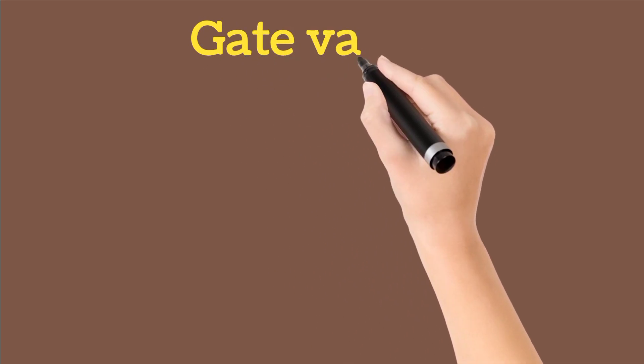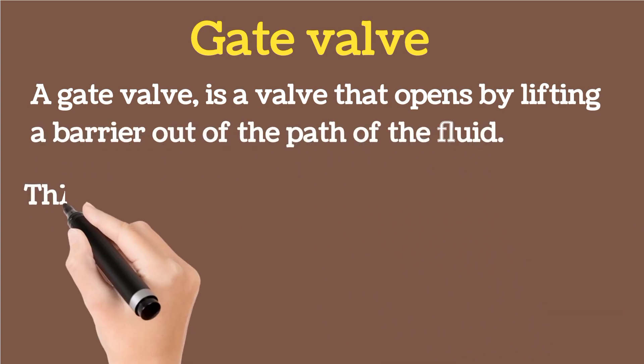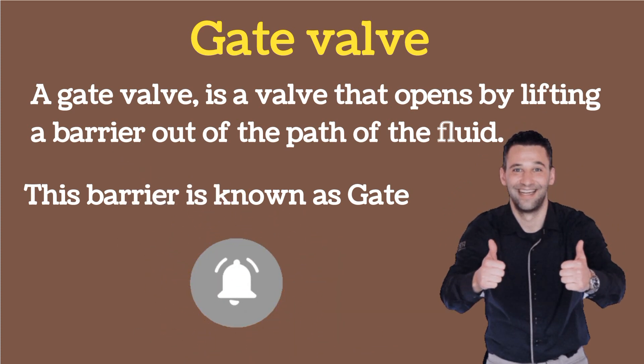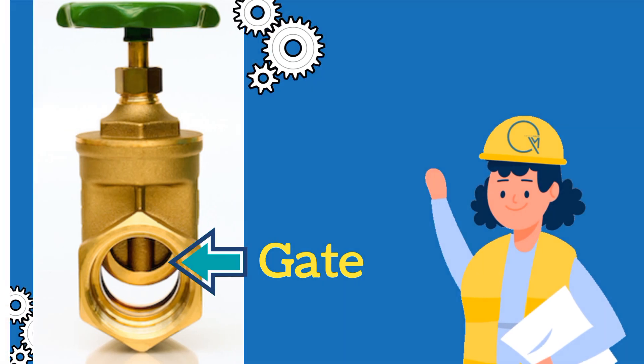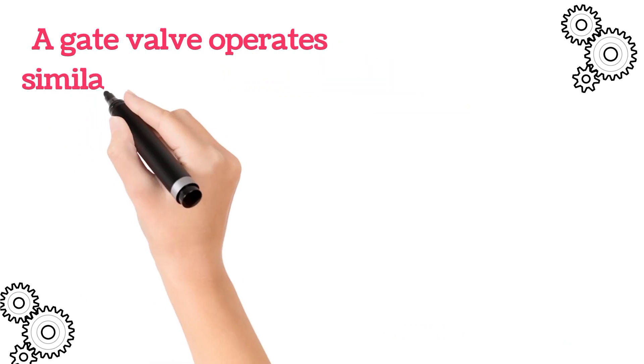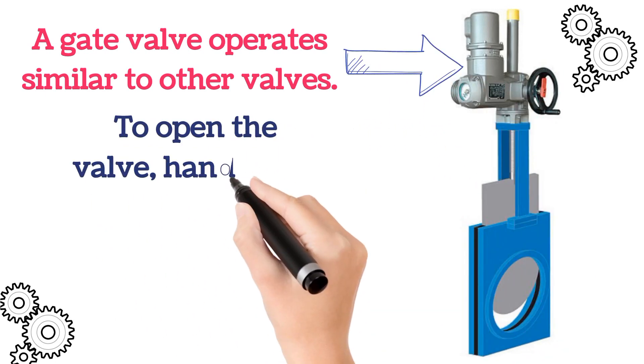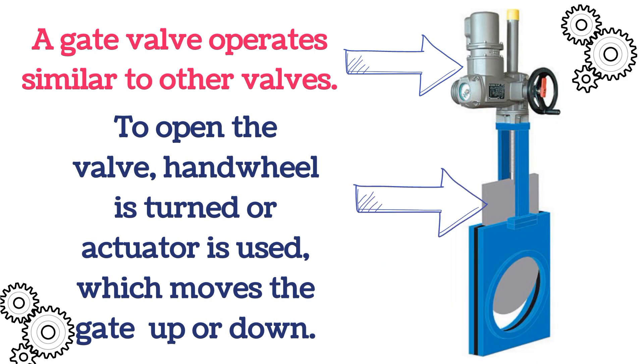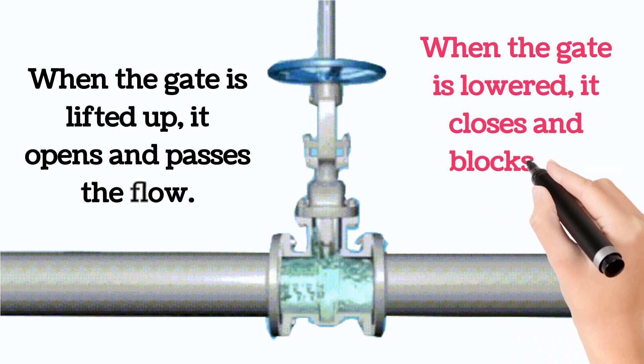Now the next valve is the gate valve. A gate valve opens by lifting a barrier in the path of fluid — this barrier is known as the gate. In the image, the barrier is shown by the arrows. The operation of gate valve is similar to the other valves. To open the valve, a hand wheel or a pneumatic actuator is used. The hand wheel or actuator moves the gate either up or down. When the gate is lifted up, the valve opens and passes the flow. When the gate is lowered, the valve closes and blocks the flow.